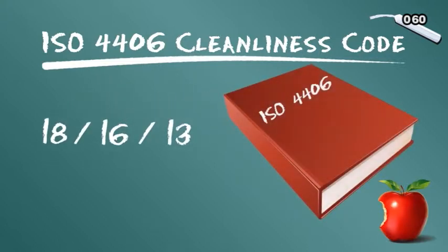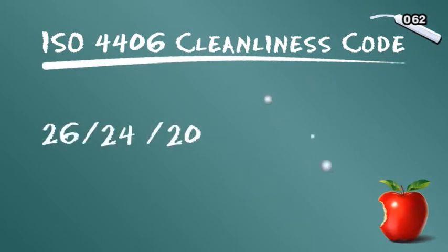Suggested ISO 4406 code cleanliness levels have been published. On the stringent side, for example, a 15/13/10 code level may be specified for servo valves with very close tolerances. A less demanding 26/24/20 would be suitable for low pressure systems with large clearances.